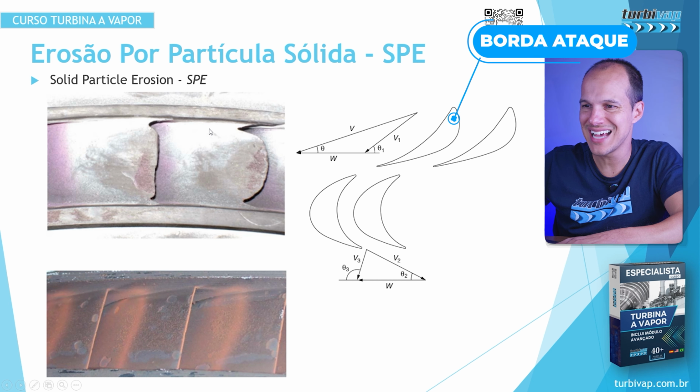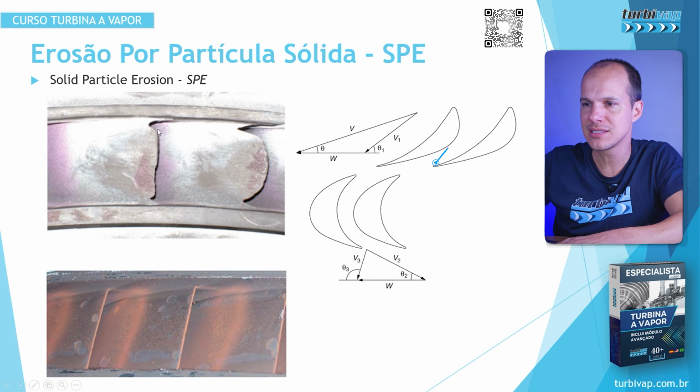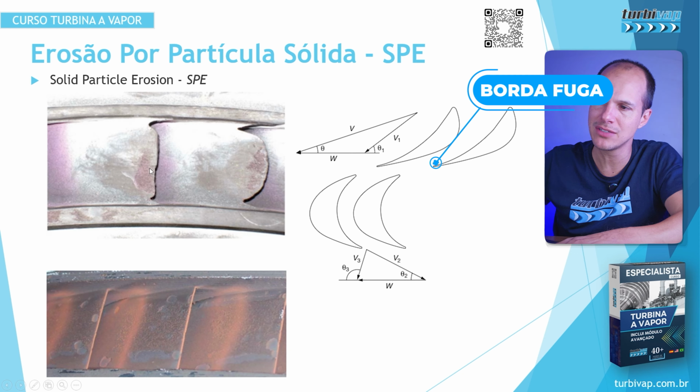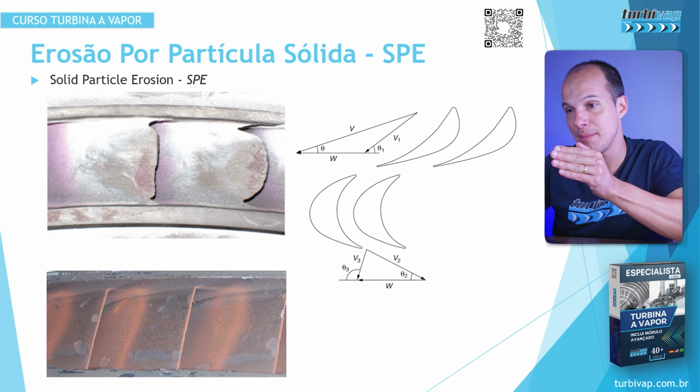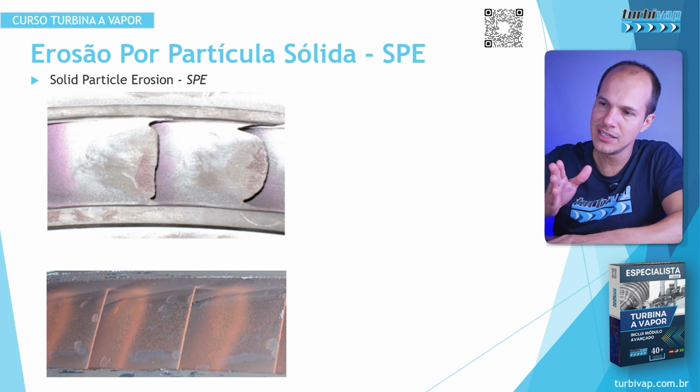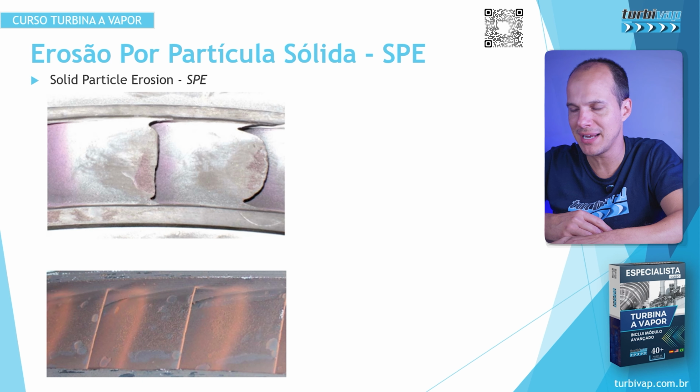The first one here shows a very characteristic degradation. This contour here, this wear here, already causes a lot of turbulence. It reduces efficiency. Why? Because it ends up projecting steam that is no longer in the direction of that velocity triangle that we who study turbomachines know. It ends up distorting that, so it does not project onto the blade at the optimum angle of incidence. For the blade, the steam, so it ends up causing a disturbance, an inefficiency.